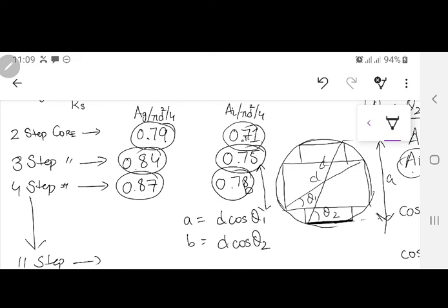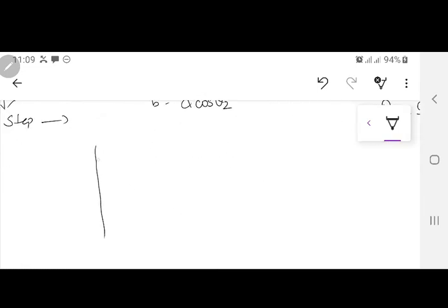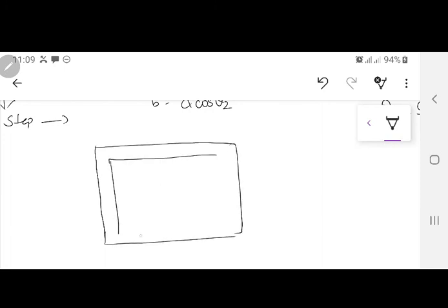Now when we have designed this overall transformer core, supposing I am just having a single phase transformer in mind, a winding was done on this one. This is a low voltage winding done first, as I have told you previously also. Why? Because it has less chances of partial discharge current flowing towards the core. The core is electrically at neutral or it is grounded.